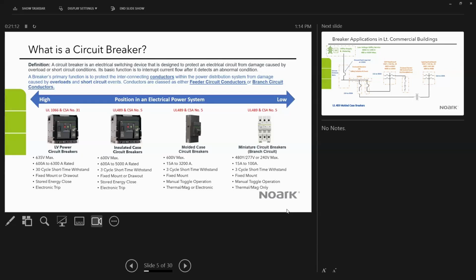Low voltage power breakers have a withstand rating based on a 30 cycle short circuit time. And that's important for coordination when we start looking at how breakers protect different parts of the circuit depending on the magnitude of the fault and where it occurs.